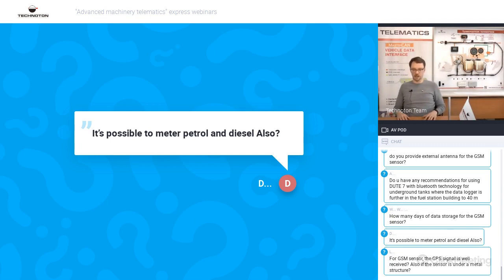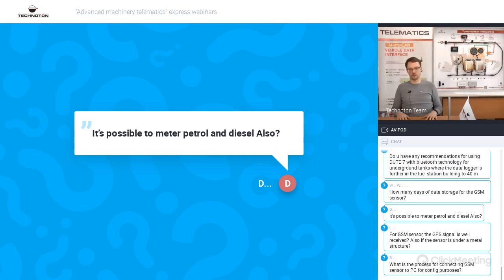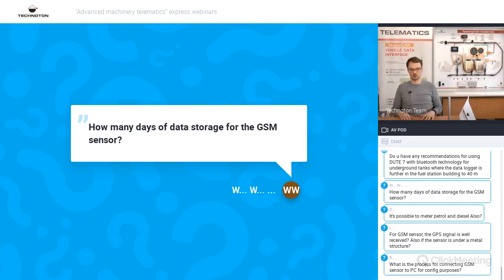For petrol and diesel, you can use a level sensor, the DUT-E S7, not the GSM one. The S7 can be used for flammable liquids like petrol because it has explosion protection and fire safety protection. As I said, no external power or additional spark protection units are used, and it has a certificate allowing us to use the sensor in zone zero, the highest risk one.